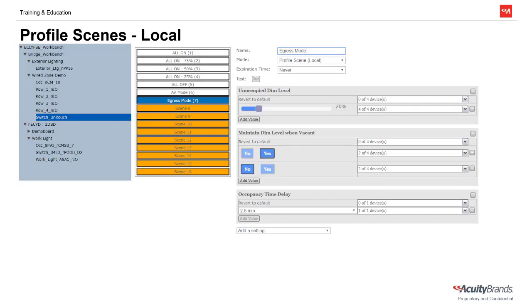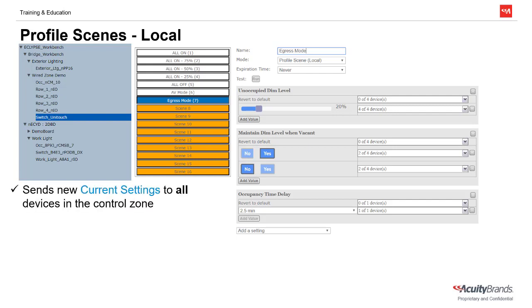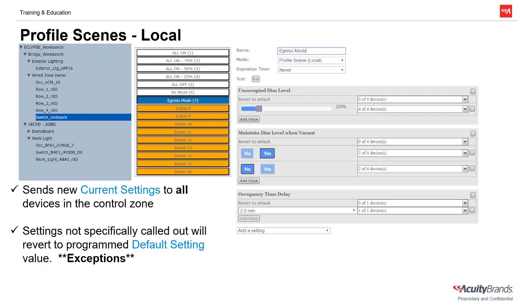Not all scenes have to make an immediate change to the various light levels in the space like Preset Scenes do. Profile Scenes give us the ability to adjust more than just the dim level of the lights in a space, but also allow us to adjust the behaviors of all the devices in this space. These changes will take place in the device's current settings as opposed to the default settings. If we just want to affect the devices in one control zone or room, we can use a local profile scene. Note that there must be a scene controller installed in this control zone, as simple wall pods cannot create or run scenes.